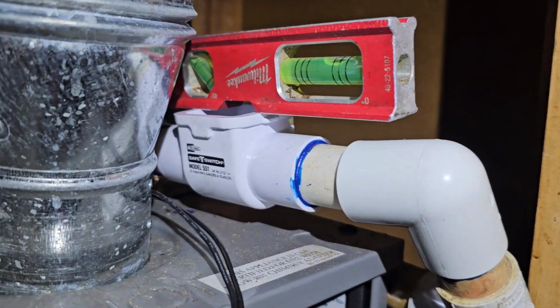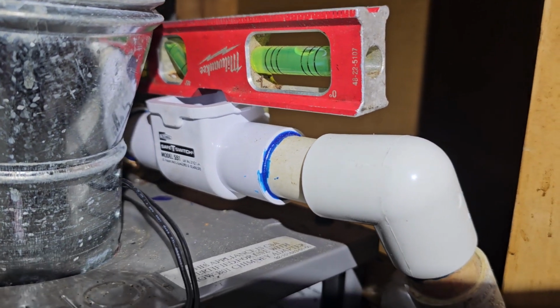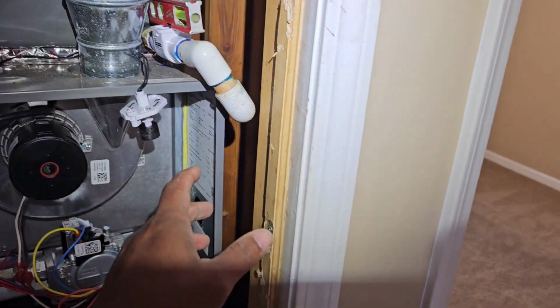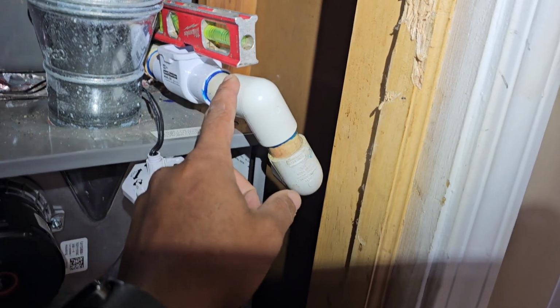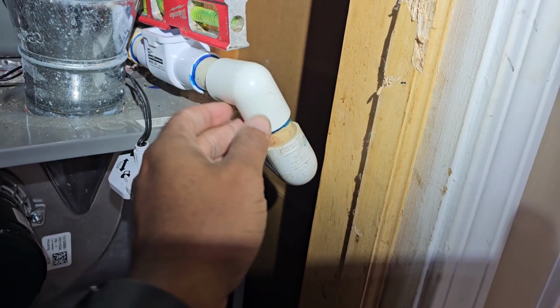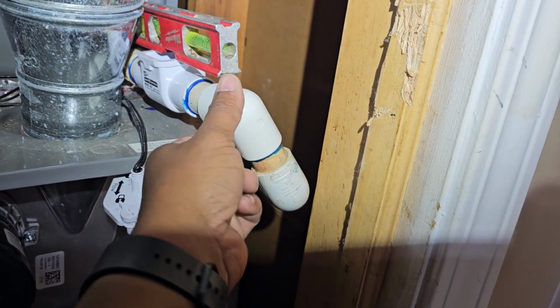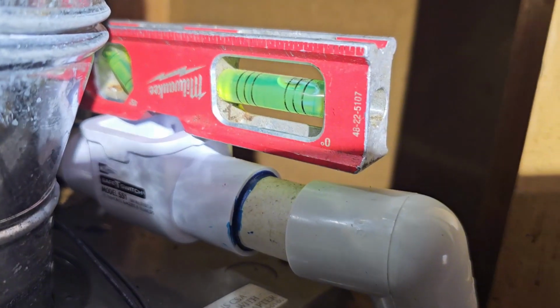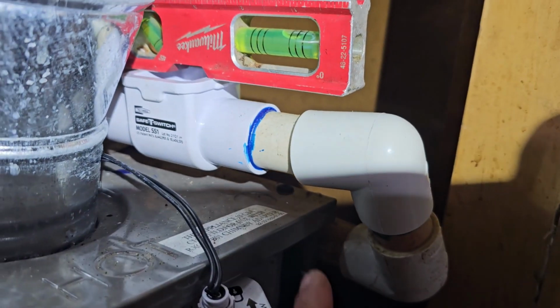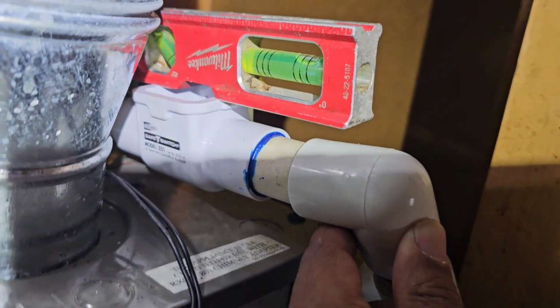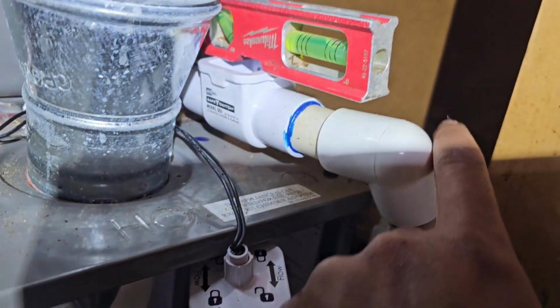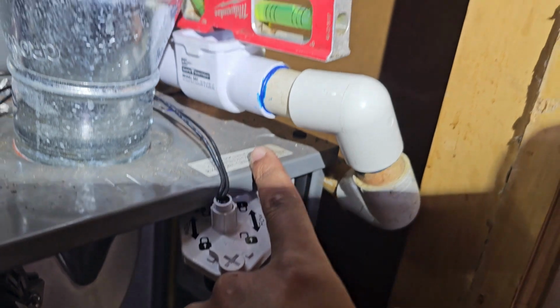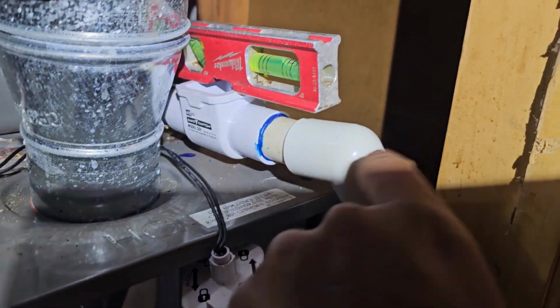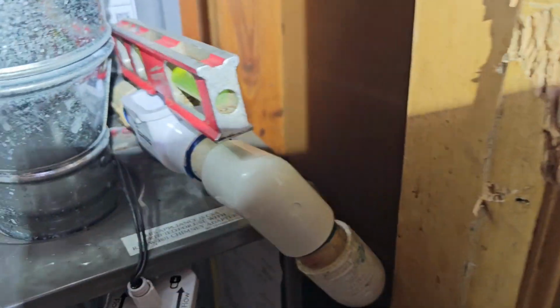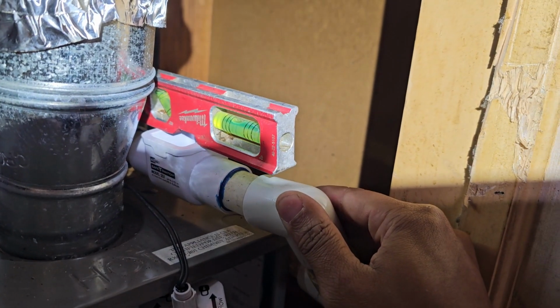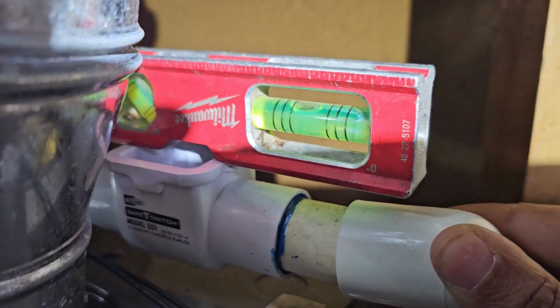Before I started flushing the drain line with water, I stood back from the unit and noticed this weird fitting right here. It's an elbow obviously, but it's at a weird tilt and angle. So I put a level up there just to check if it was pitched correctly. It's kind of back-pitched towards the coil, so it wouldn't drain properly if I left it like this. What I'm going to need to do is get some hole strap, screw it here and on this corner, and pull this down to get a good bit of fall.